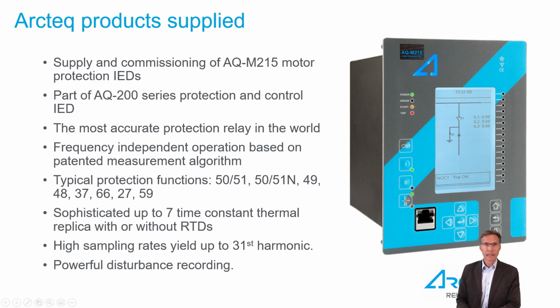Interesting for many industrial applications is the harmonic content in the system. So the high sampling rate in the 200 series relays allows us to record harmonics up to the 31st. So on the disturbance recording, you may see, for instance, issues on the variable frequency drives causing harmonics, etc. This can be quite powerful analysis.